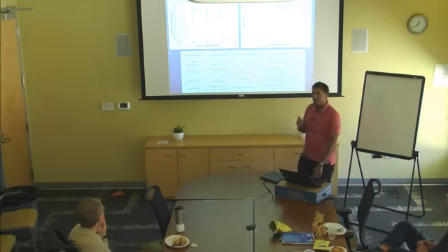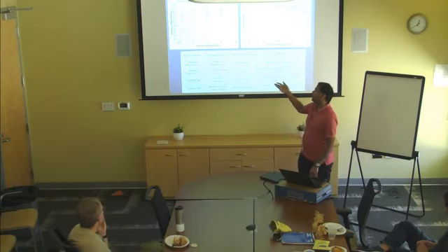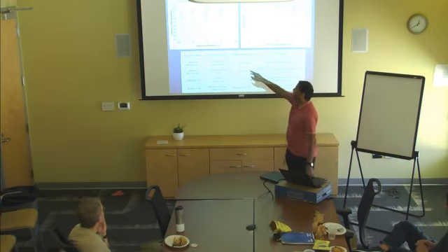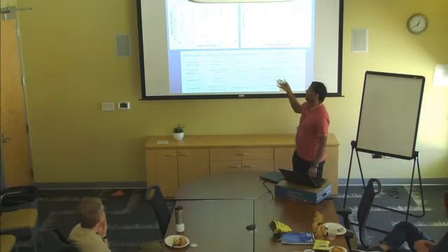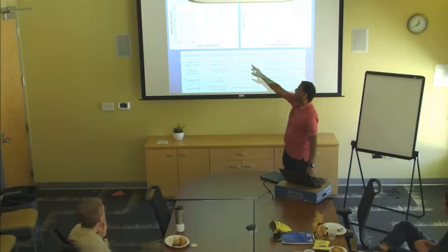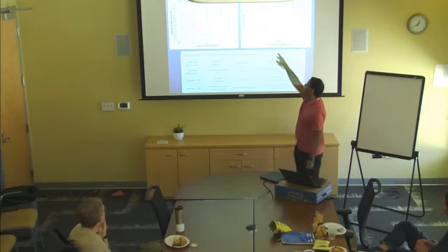Another thing I want to show you is that the duct effectiveness is a non-trivial effect. If you see the 40% point for the blue line, the equipment COP may be like 3 for that point, but because the delivery effectiveness is like 40%, the system COP drops down to around 1.